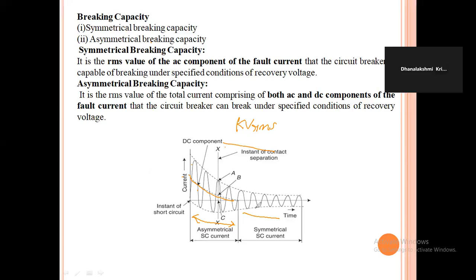So this is the waveform. This is the AC, this is the DC offset current. This is the DC component, and both AC and DC components of the fault current together are called asymmetrical. So this section is called asymmetrical breaking capacity. After that, the DC component dies out, and only the AC component of the fault current is present. So this is the symmetrical AC current. The short circuit current contains a DC component which dies out gradually, as shown in the figure.